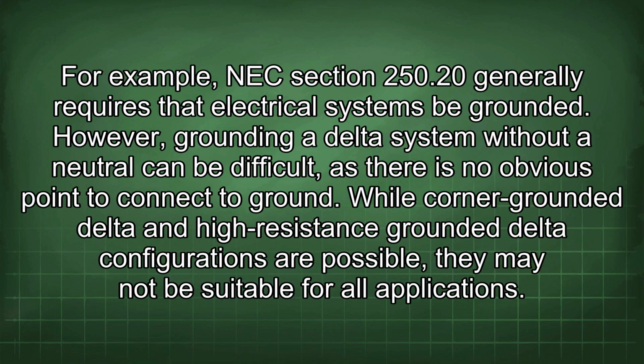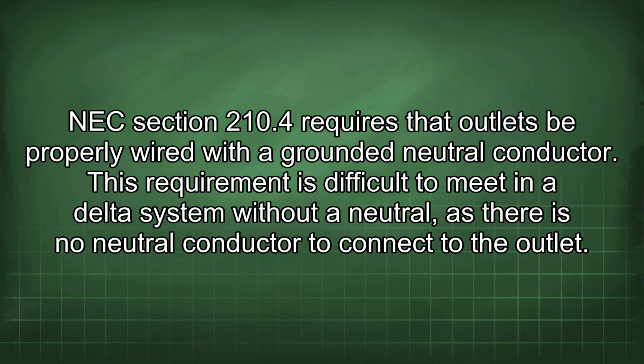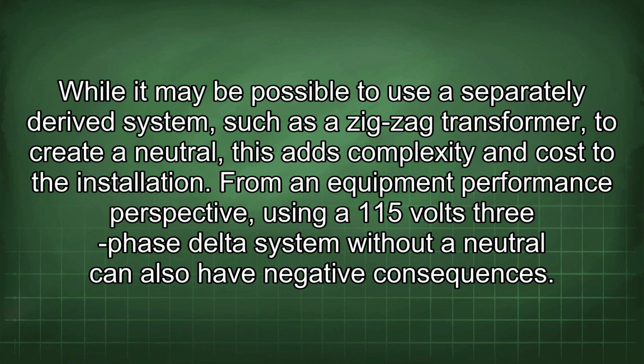For example, NEC section 250.20 generally requires that electrical systems be grounded. However, grounding a delta system without a neutral can be difficult, as there is no obvious point to connect to ground. While corner grounded delta and high resistance grounded delta configurations are possible, they may not be suitable for all applications. NEC section 210.4 requires that outlets be properly wired with a grounded neutral conductor. This requirement is difficult to meet in a delta system without a neutral, as there is no neutral conductor to connect to the outlet. While it may be possible to use a separately derived system, such as a zigzag transformer, to create a neutral, this adds complexity and cost to the installation.